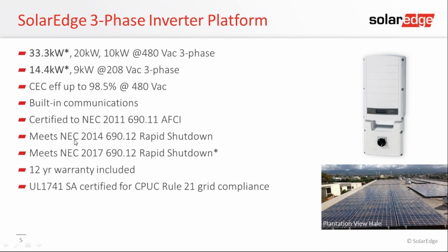In the 2014 code in the US, what we learned is it wasn't very well defined. Basically, in the US, we said you're going to have some DC conductors coming from the roof. We need to control that voltage to less than 30 volts within 10 seconds, and it has to be labeled. And that was it. It didn't tell you anything about accessibility or where the device has to be placed. And it gave us a boundary around the array, within 10 feet of the array. So most people were getting around this requirement by putting inverters on the roof, because now it's AC conductors coming off of the roof, and per UL 1741, they meet all the rapid shutdown requirements.